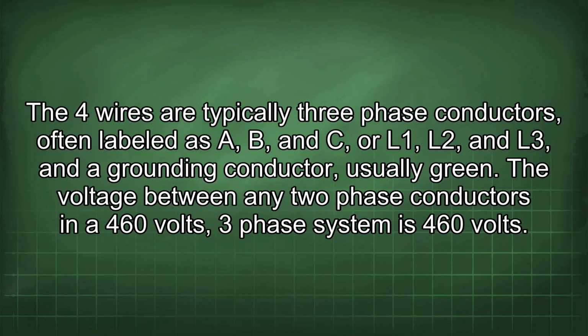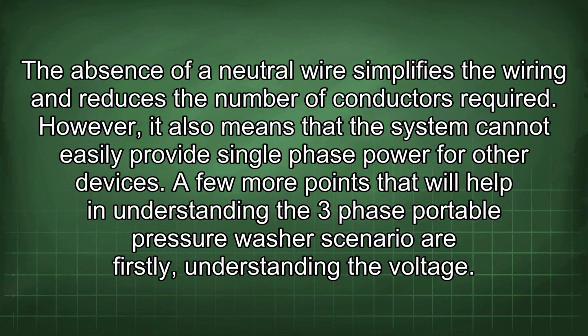The four wires are typically three-phase conductors, often labeled as A, B, and C, or L1, L2, and L3, and a grounding conductor, usually green. The voltage between any two-phase conductors in a 460 volts three-phase system is 460 volts. The absence of a neutral wire simplifies the wiring and reduces the number of conductors required. However, it also means that the system cannot easily provide single-phase power for other devices.